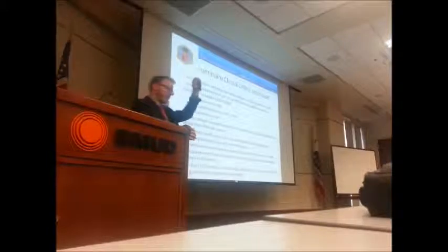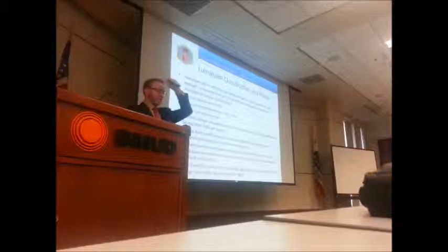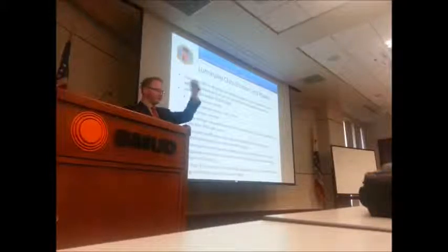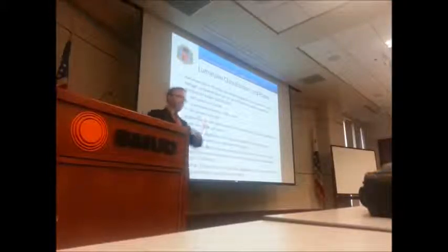Same with some HID luminaires that have multi-watt ballasts. So what we'll do is accept the peel-down label. Inside the luminaire housing, it says the maximum rated relamping wattage is whatever is printed on the label, and you can have multiple labels that either the manufacturer or the installer can peel down. The first one says 42 watts, the next says 32 watts, the next says 26 watts. You peel it down until it says 26, put a 26-watt lamp in it, and you're good to go.